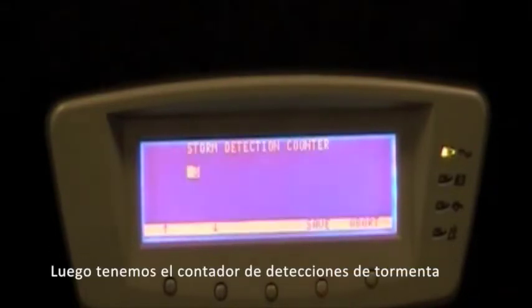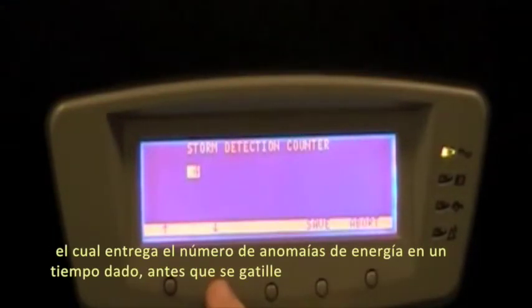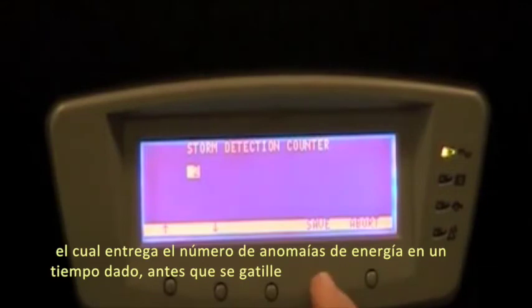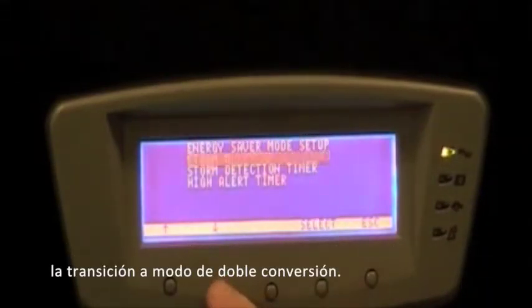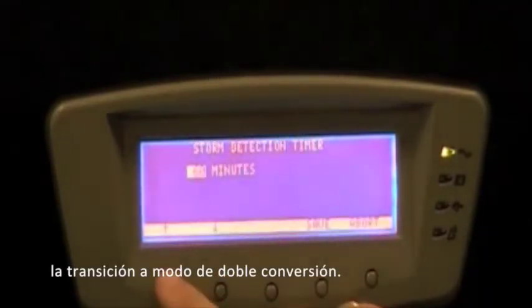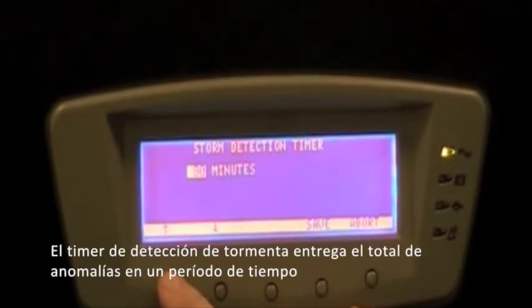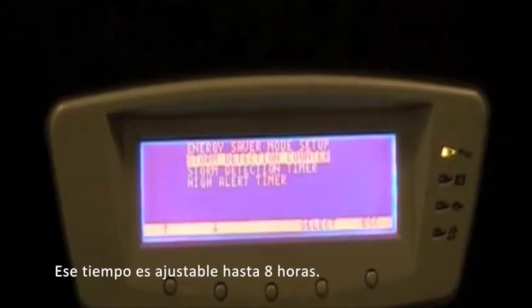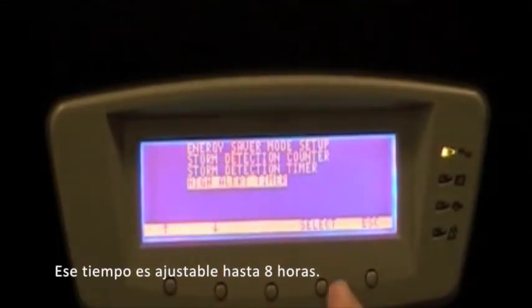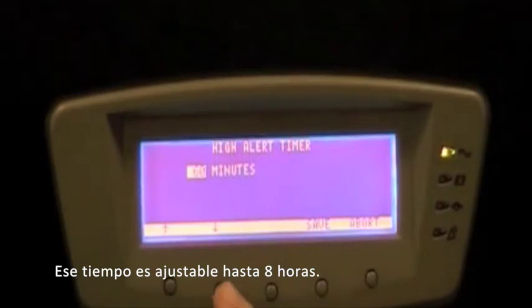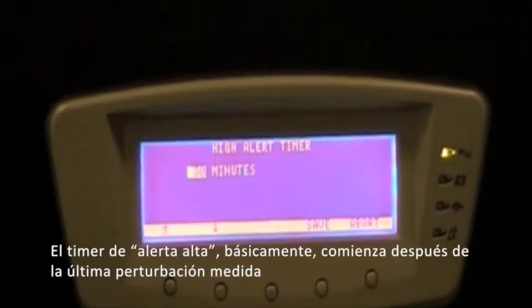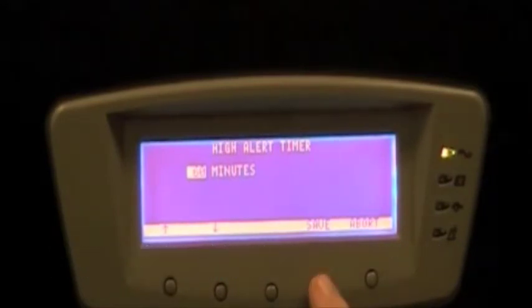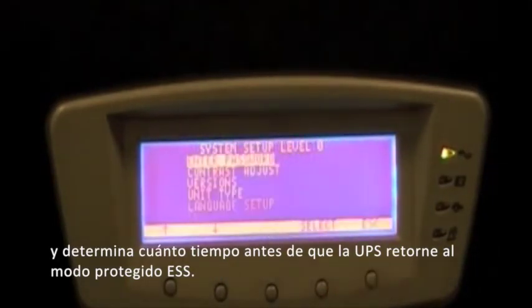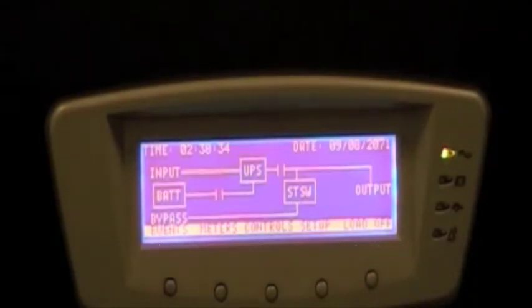Then we have a storm detection counter. This counts the number of power anomalies within a given time before a transition to double conversion mode is triggered. The storm detection timer counts the given number of anomalies within a given period of time. That amount of time is adjustable up to 8 hours. The high alert timer basically starts after the last sensed disturbance and determines how long before the UPS returns to ESS protected mode.